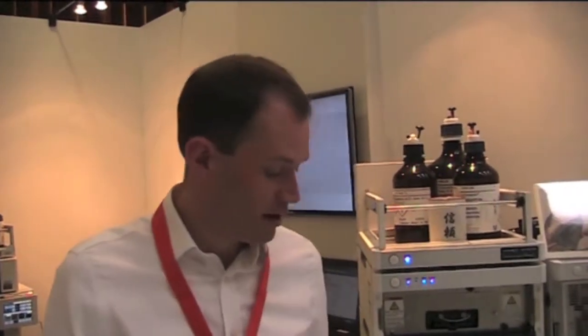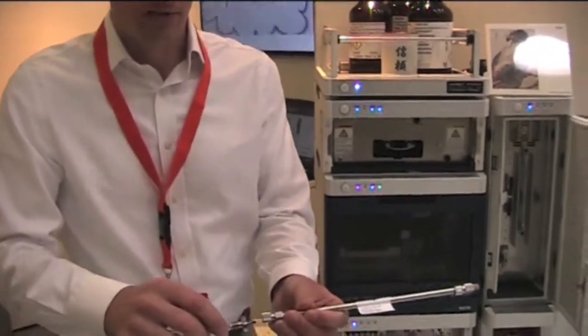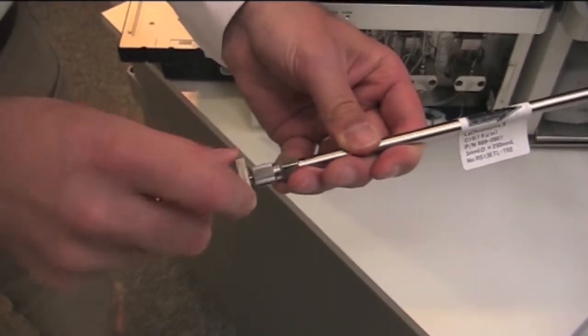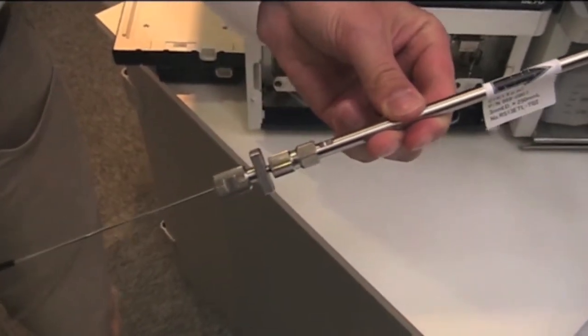And what it does is it avoids any extra dead volume between the end of the capillary and the frit. It does up very easily, just like so. And this is now pressure stable to 1400 bar.